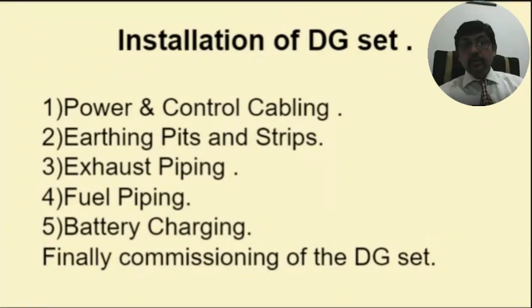Exhaust piping is for letting the smoke which comes out of the engine out to the atmosphere. And the fuel piping is the connection between the fuel tank of the generator and the engine. And finally, the battery charging is required. Batteries are basically sent in uncharged condition, so they have to be charged. Of course, the diesel has to be filled. And then finally, the commissioning of the DG set takes place. And from there, the warranty starts. Yes, next.